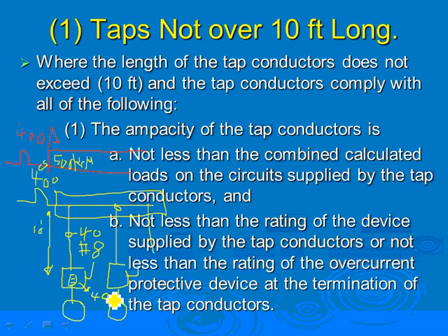So that's another condition. If you are to tap from a conductor, the conductor cannot be less than 1/10 of the overcurrent device. It has to be enclosed in a conduit, protected. It has to land on an overcurrent device that is rated based on the ampacity of the conductor. Done deal.